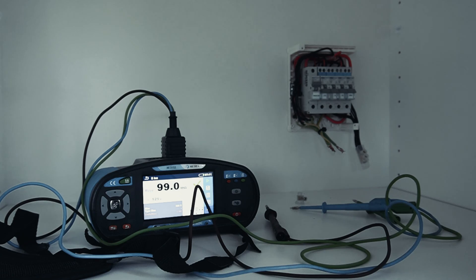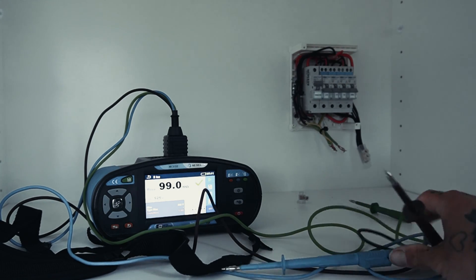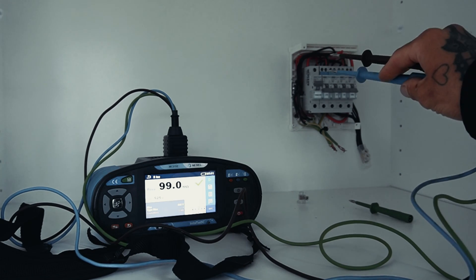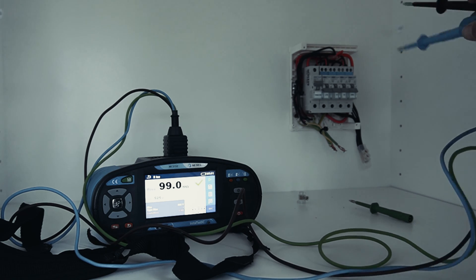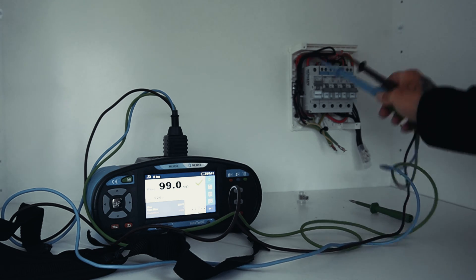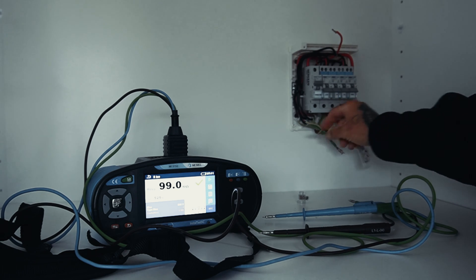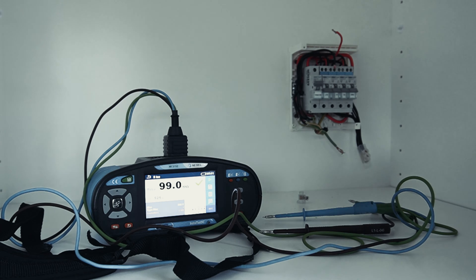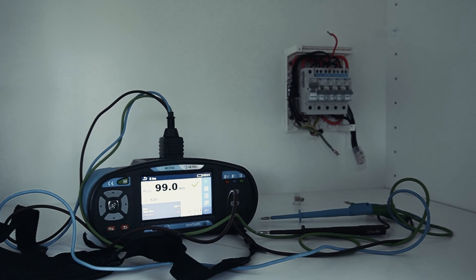This is the multi-function tester we used — the Metrel MI 3152. We worked our way through doing our IR tests on all circuits and we found on P2 that there was a dead short on line to earth. The guys are now going to walk through and disconnect that circuit to see if we can find the fault.